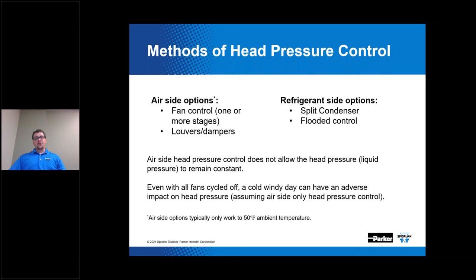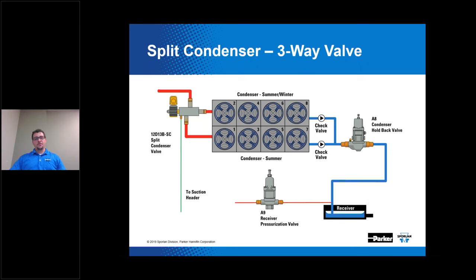Now we'll discuss the different methods of head pressure control, which include air side and refrigerant side options. Air side options consist of fan control using VFDs or cycling fans on and off in stages — airflow across the condenser being one of the three factors that affect condenser capacity. Refrigerant side options consist of splitting the condenser or flooding of the condenser. Air side head pressure control does not allow the head pressure or liquid pressure to remain constant during varying low ambient temperatures.